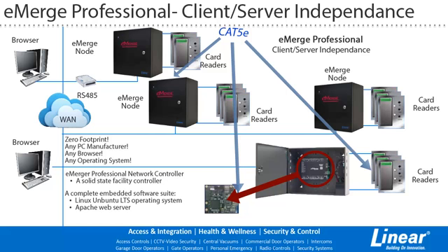Lastly, we use the Cat5e. Our IP-based solution uses the most standard and readily available network cabling. This allows us a lot of flexibility from the installer perspective. We can install the individual nodes, manage the individual door hardware close to the edge, close to the doors themselves, or they could still be home run back to the data or IT closet somewhere, and they just need a simple connection, each one to your router or switch. eMerge will also work very well in a wide area network.